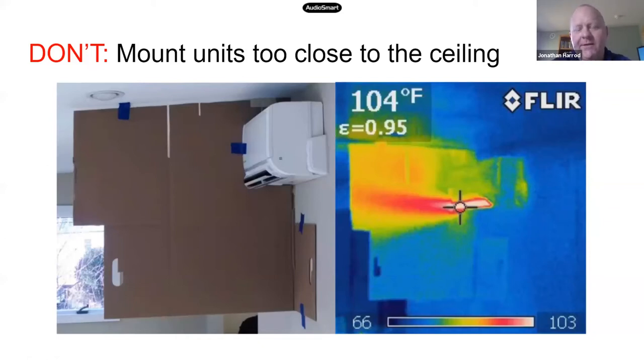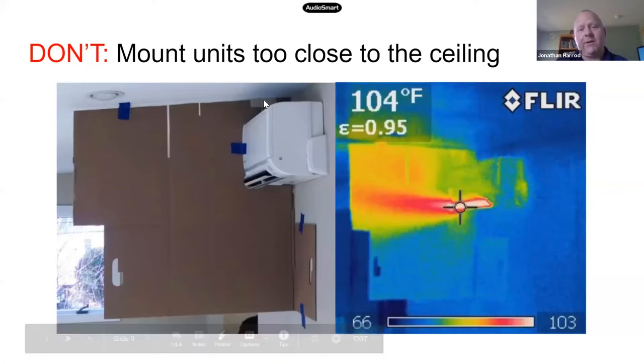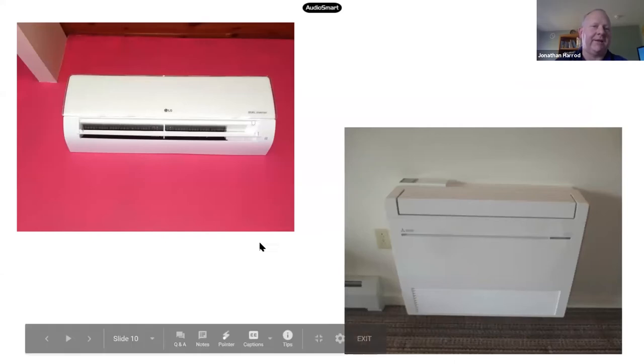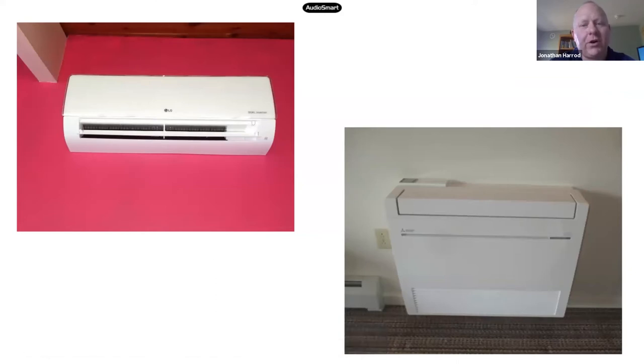And this effect is exaggerated when the unit is pressed right up against the ceiling. You don't get good airflow, you don't get good mixing. And so what happens is that you don't get good heat exchange because the air that you're bringing back into the unit is already warm. It doesn't have as much ability to absorb heat as if it were room temperature, you know, 66, 68 degrees. So the solution, if you're going to install a high wall unit, is to install it ideally at least 6 inches down from the ceiling. And that's what we have in this left picture here. Plenty of room for mixing to occur.